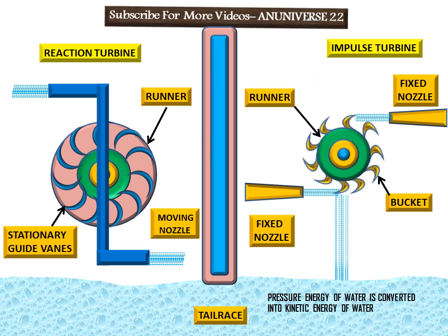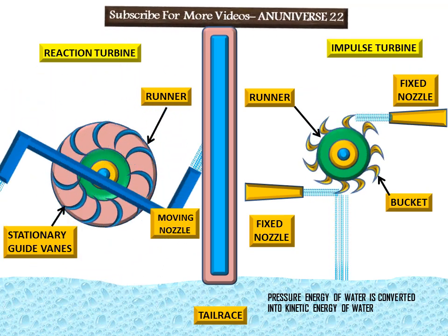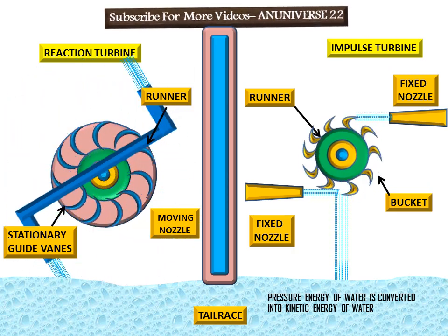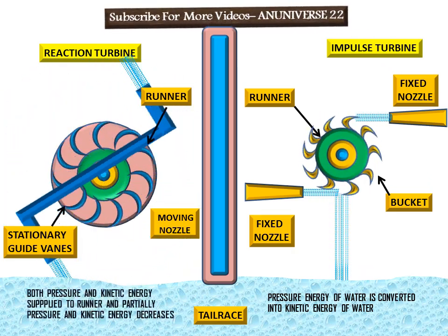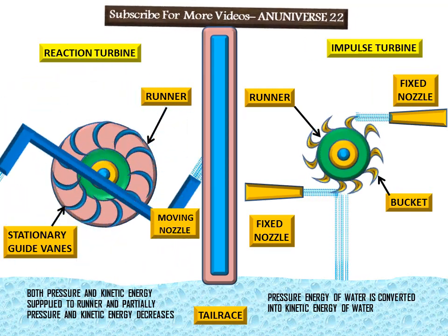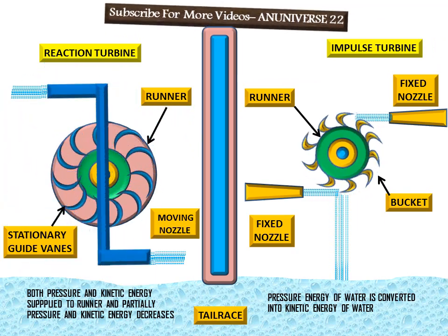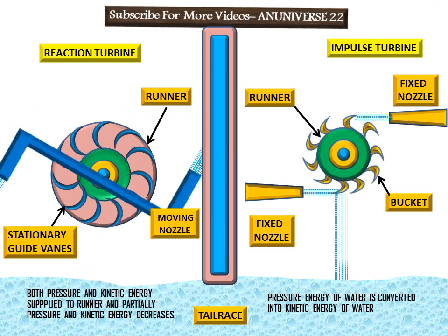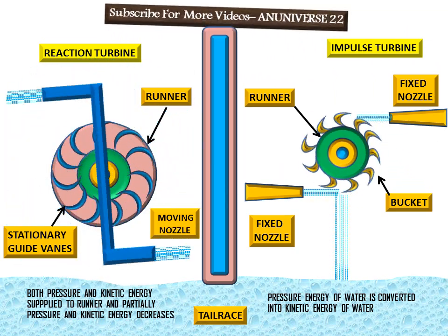In the case of the reaction turbine, there is a moving nozzle. Here, only part of the total available head is converted into kinetic energy, and the rest remains in the form of pressure energy. The pressure of water entering the turbine is always above atmospheric pressure, and as water flows through the turbine, its pressure changes. The flow of water from the inlet to the tailrace remains under pressure throughout.